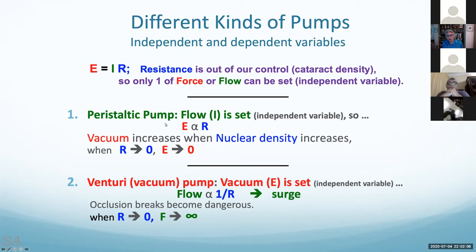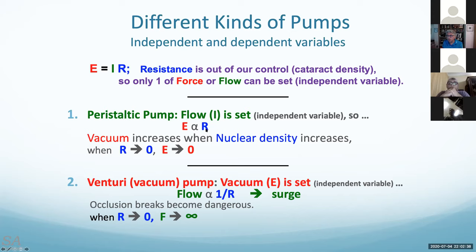In peristaltic pumps, flow is set as the independent variable. On phaco machines like Alcon or AMO, you set the flow rate, which becomes the independent variable. You cannot control R, the resistance of the aspirate. So E, the vacuum buildup on the phaco machine, is proportional to resistance — meaning that as you aspirate denser pieces of lens, the vacuum will build higher. The rate at which it builds is determined by how fast the flow rate is.